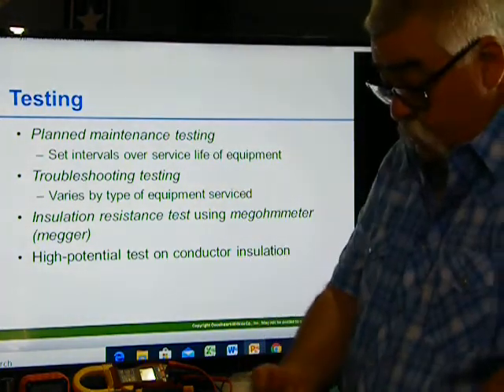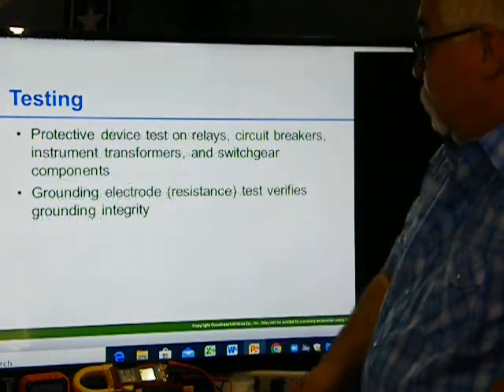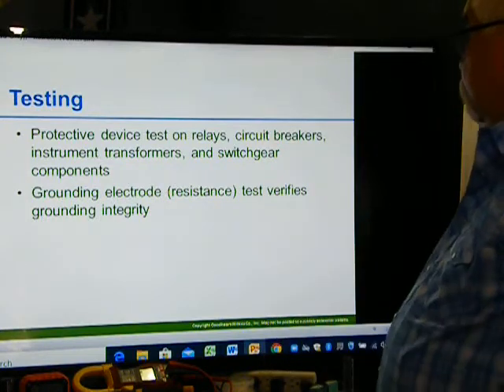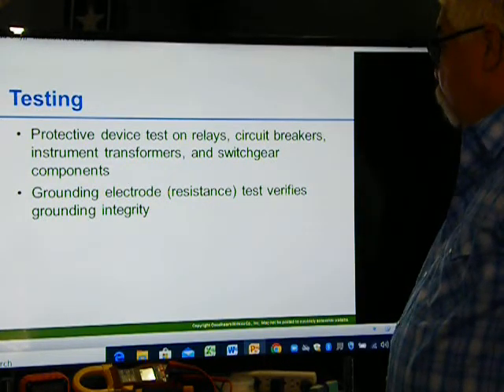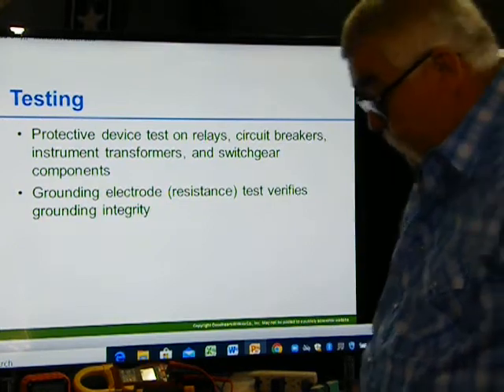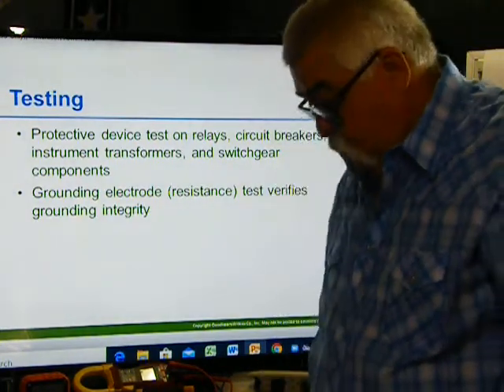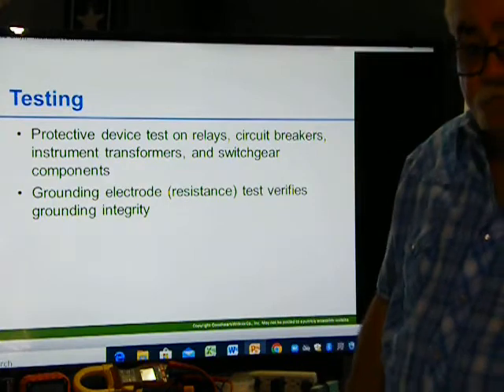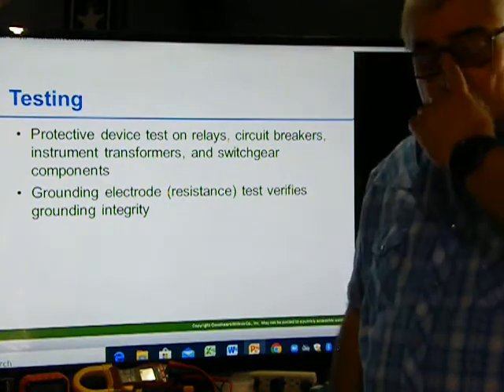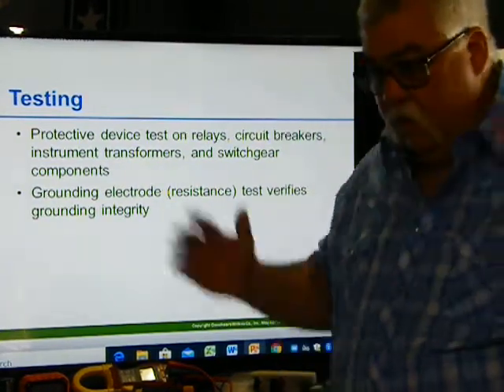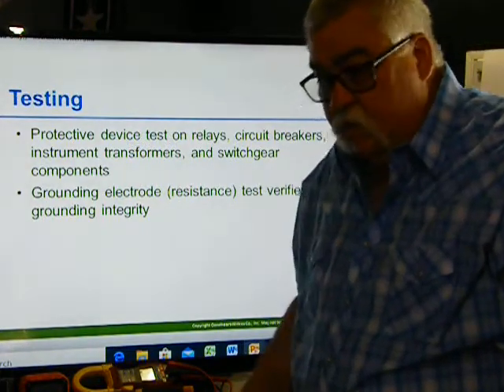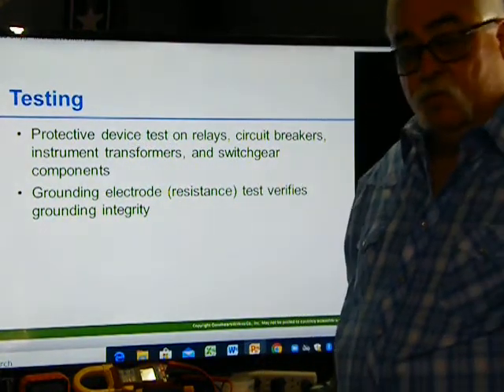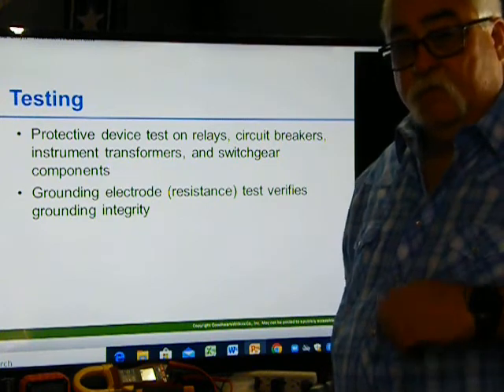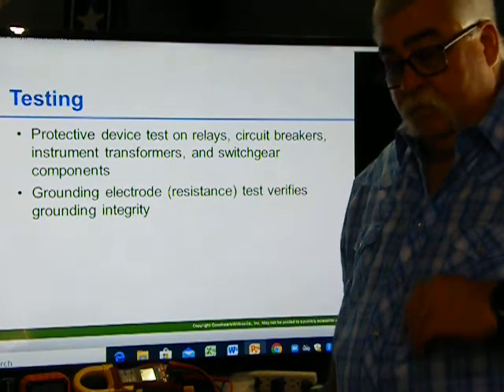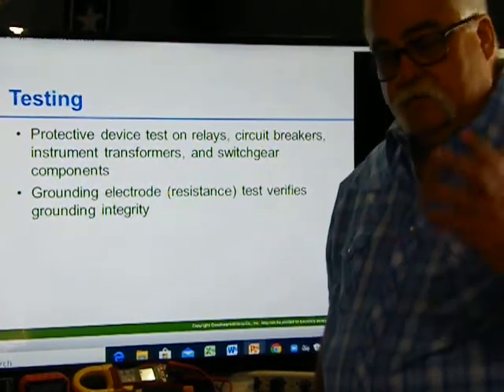Protective device test. Protective device test on relays, circuit breakers, instrument transformers, and switchgear components. Okay, that's like your GFIs. When you walk over to the GFI and you hit the trip button, you're testing it. You know, we used to do that once a year for our big air breakers. We test them once a year, or sometimes we test it like in the hospital. We tested them every month. Okay, or every 3 months.